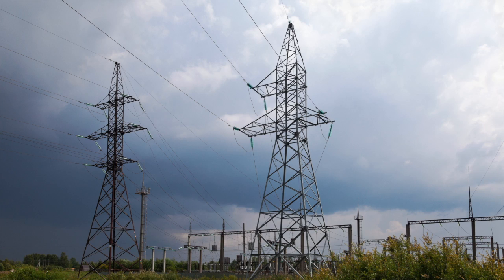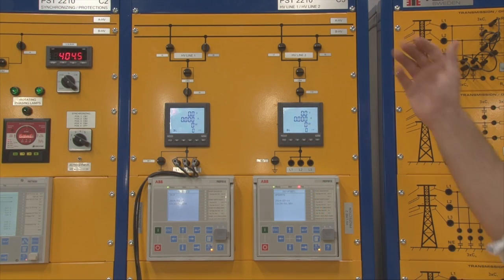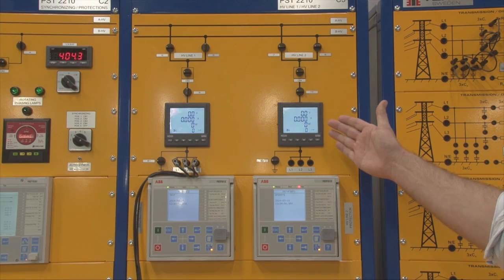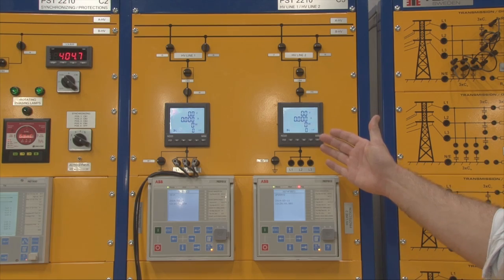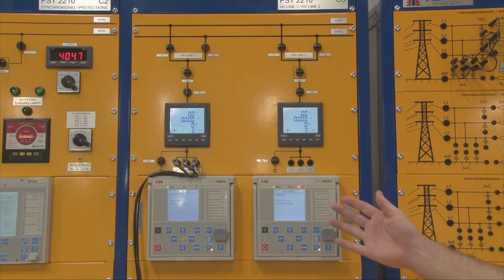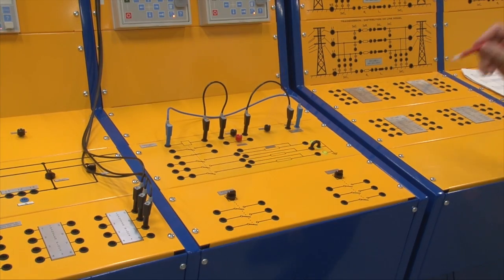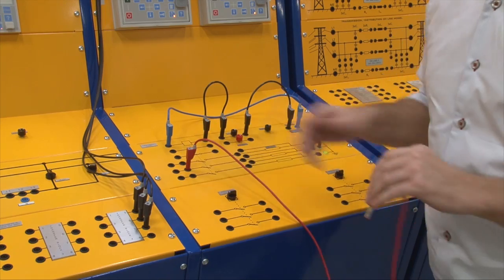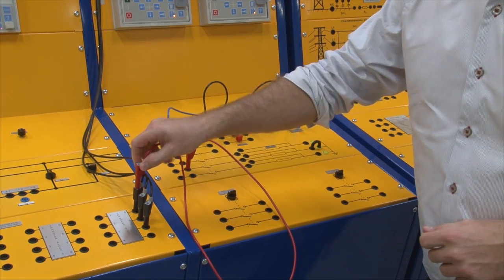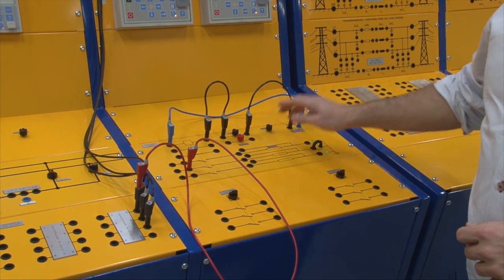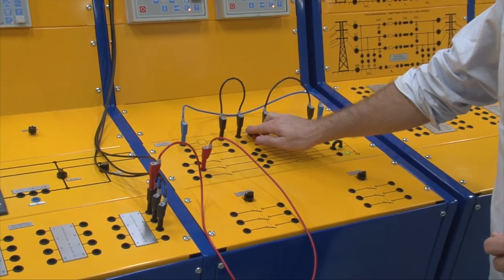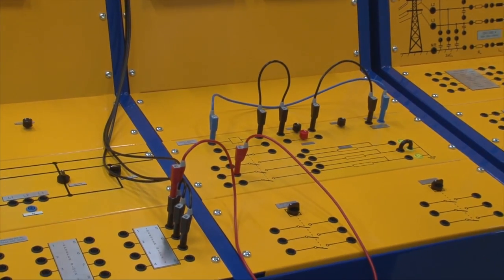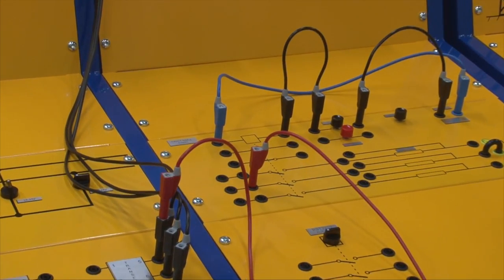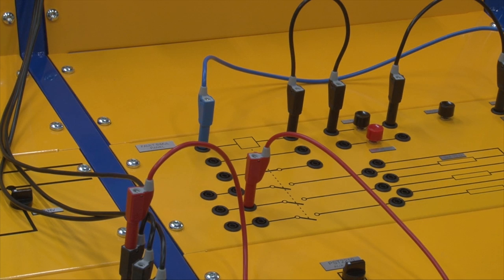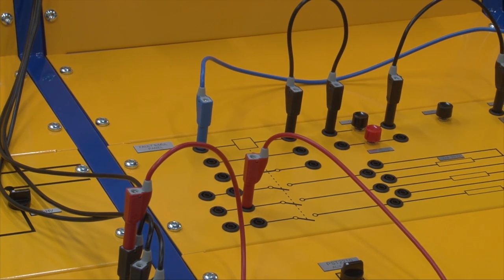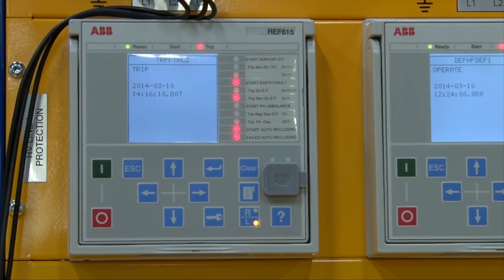Dual outgoing lines allow for different system configurations. Both are monitored for fault conditions by dedicated IED line protection relays. The fault simulator panel is used to connect and control numerous true-to-life faults, scaled down for safety, of course. Connecting real faults lets us study and understand the numerous protective functions of each relay. Simultaneously, it allows us to identify and practice the correct course of action to clear and rectify problems when faced with a fault situation.